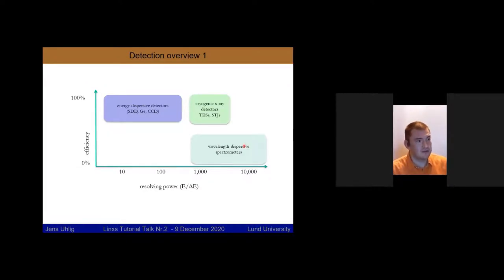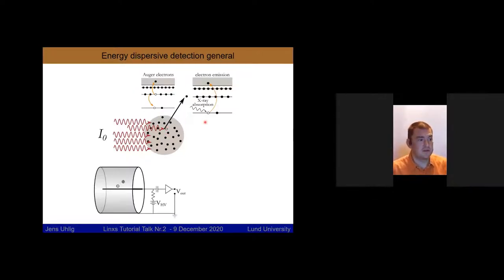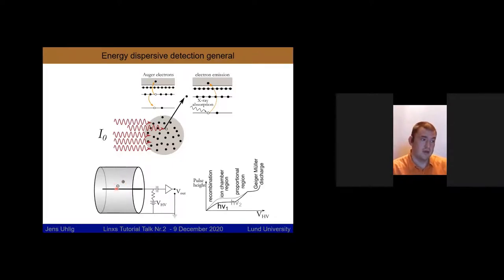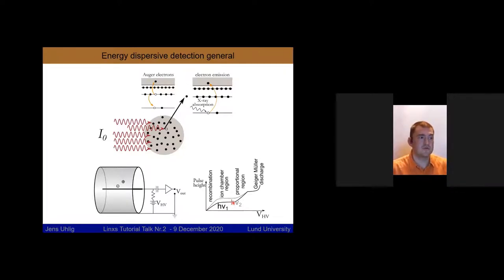There are three different types of detectors. The first are energy dispersive detectors, which absorb the photon and produce a fast electron. In an ion chamber, photons ionize a gas and the charges are accelerated. At a low voltage, the ions recombine. In a proportional range, all charges are extracted one by one — one photon, one electron. At higher voltage you get amplification, and in the Geiger counter regime you get one click per photon.